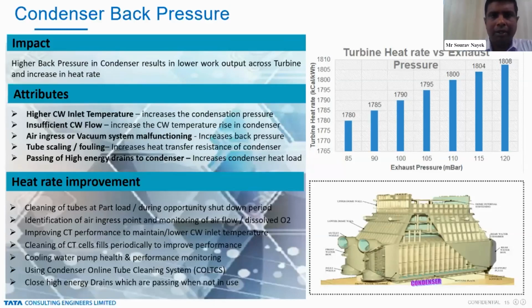I will first talk about the condenser back pressure, which has a large impact on the plant heat rate, because as the back pressure increases, we will see a large increase in the heat rate, and that will contribute to lower turbine output and this will have an overall life cycle cost increase of the plant. So we will talk about what are the attributes of the condenser back pressure increase. These are mainly the points which we will talk about.